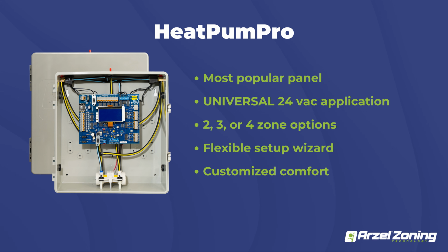So really for any kind of operation you guys would have or any system you have, you can use just single stage heat cool thermostats and it's going to handle all that staging internally. So it's a really nice, well-rounded panel. It was really made so that you guys can use really inexpensive thermostats but still get that sophistication of your high-end thermostats because it's all built into the panel. So like I mentioned before, it's going to ship with that outdoor air sensor and a leaving air temperature sensor. And this panel goes up to 4 zones. So it's going to be a 2-zone, 3-zone, or a 4-zone. So it pretty much covers you guys for just about any application in the residential market. Typically, you're not going to do more than 4 zones residentially. You're going to have too small of zones when you start getting bigger than that.